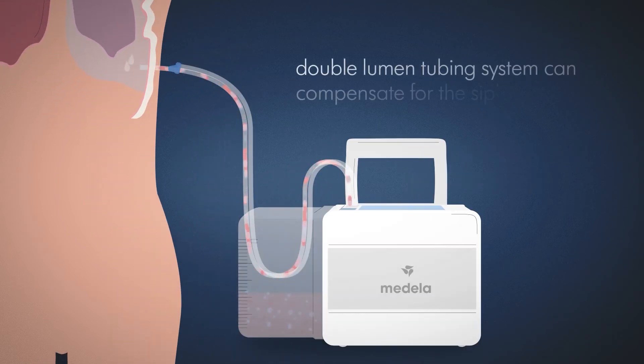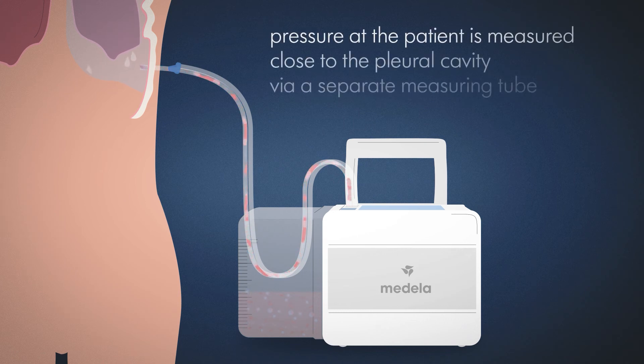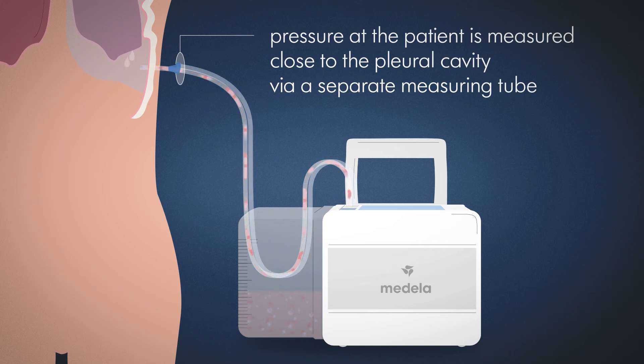With a double lumen tubing system, digital devices such as Thopaz+ can compensate for this effect. In this case, the pressure at the patient is measured close to the pleural cavity via a separate measuring tube that is not carrying any fluids.